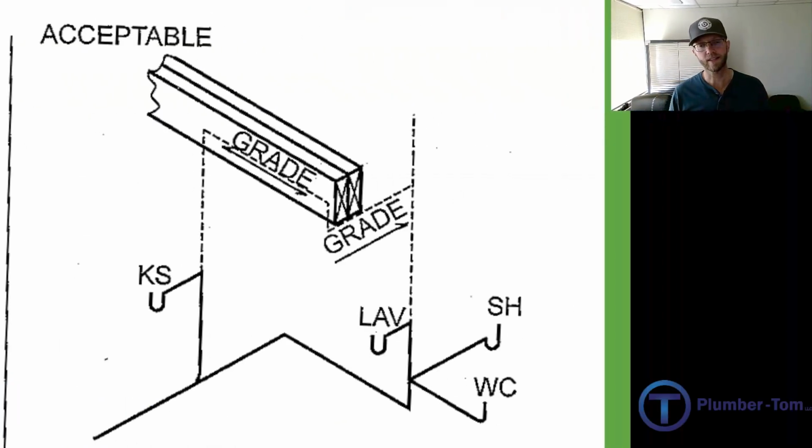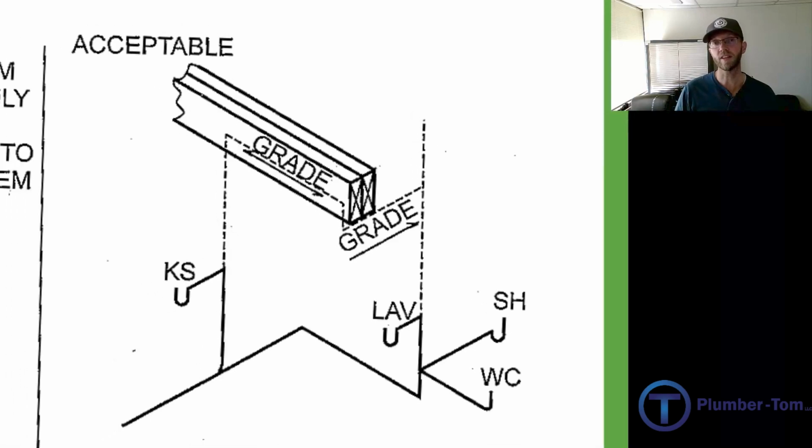Here's an interesting example on a diagram. There's a kitchen sink, and we need to run a vent for that, but there's a big beam in the way, so we can't really go through that. You can see here that that kitchen sink vent is actually reverse graded. It flows down and connects into the vent for the bathroom group. As long as that vent connects to a drain, then it doesn't matter which direction that slope goes. Now, this is kind of a rare exception, but it's an acceptable way of running pipes. Even if there's reverse grade, you can do this if it connects to a drain.